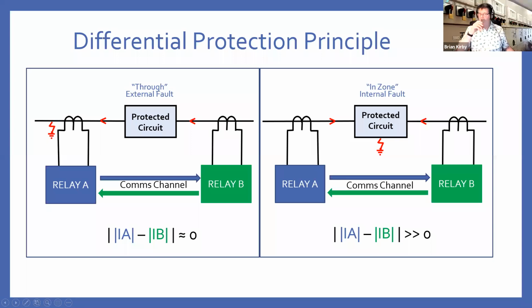Differential protection, as I mentioned already, you're looking at your protected circuit. If you have a fault external to your circuit, then the current flowing through, when you do a comparison of the 2, the difference will be approximately 0. There will be some small errors due to measurement errors, etc., perhaps small timing errors, but you expect the current for your differential to be quite low.